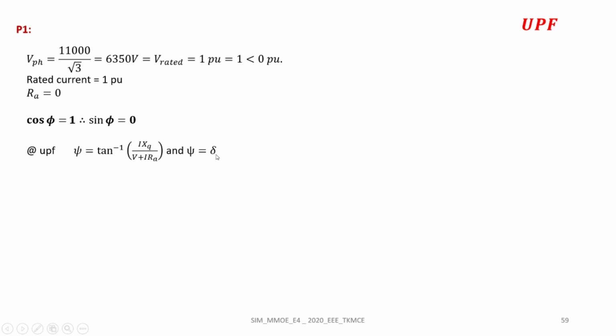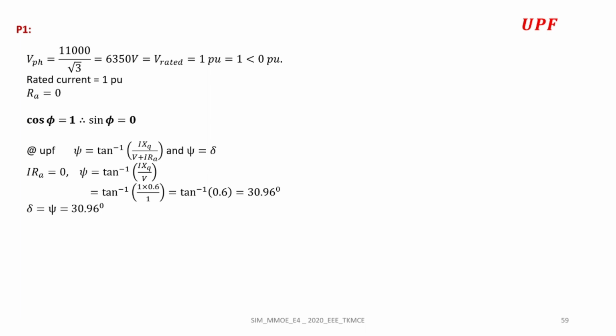And the angle relations are psi is equal to delta. As RA is 0, this expression will reduce to tan inverse IXq divided by V. Substituting different parameters, we can obtain psi as 30.96 degree, which is equal to delta. Now we can compute ID and IQ. ID is equal to I sin psi, which is obtained as 0.51 per unit, and IQ is obtained as 0.86 per unit.